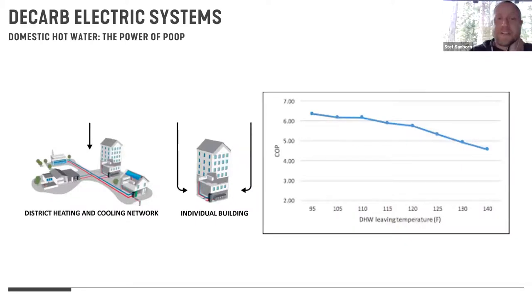The beauty of doing this, and why it matters a lot, is the coefficient of performance. I was talking earlier about how we can see air source heat pumps in cold climates, and they might have a COP of 1.5 to 2.5 during those cold outside air temps. When we look at a better source, whether it's ground source, sewage source, or energy recovery source, finding a really quality place to pull energy from is dramatically going to push up our COP.